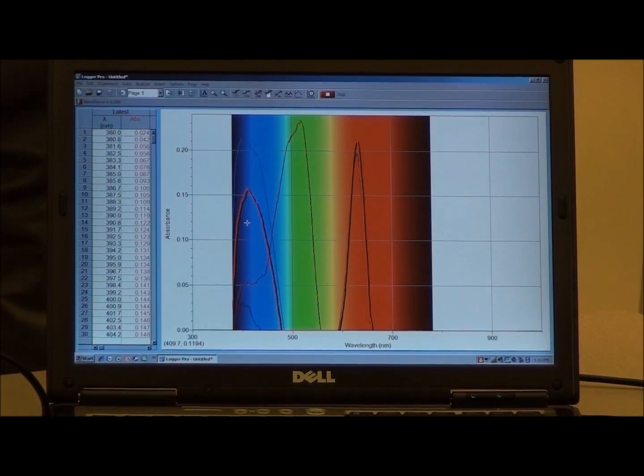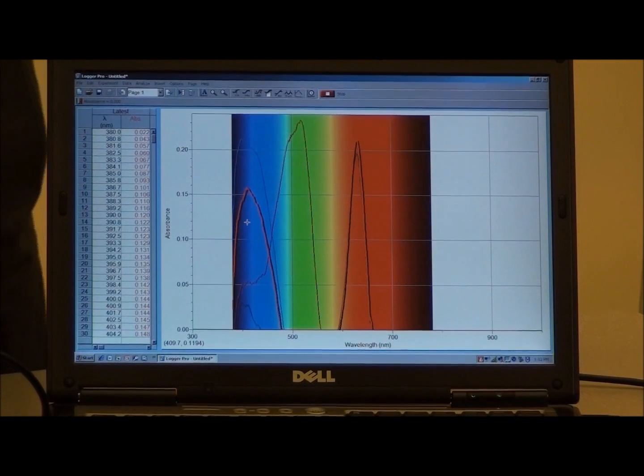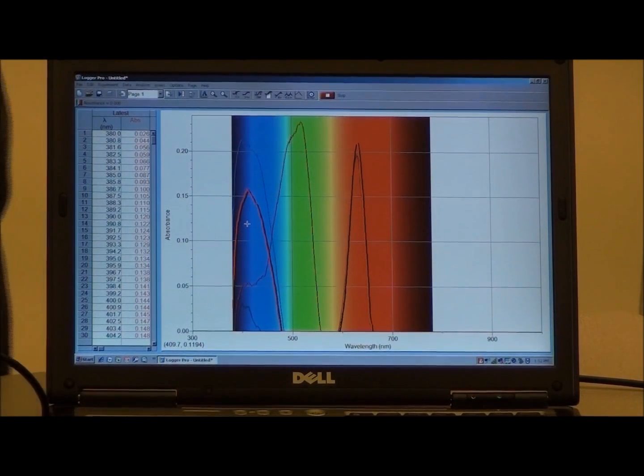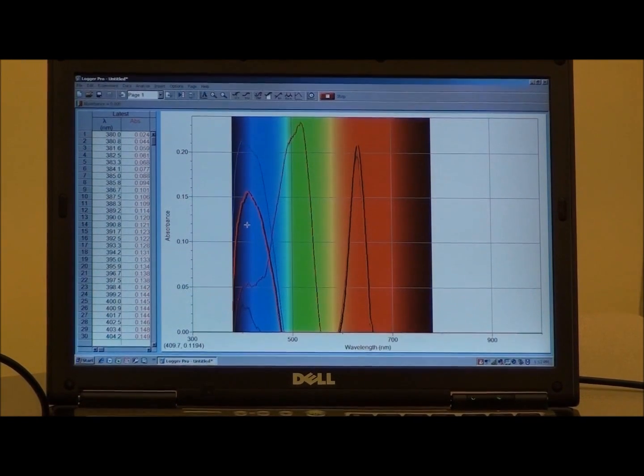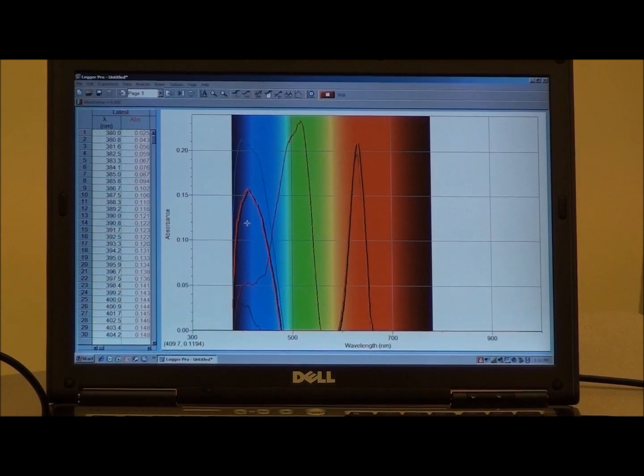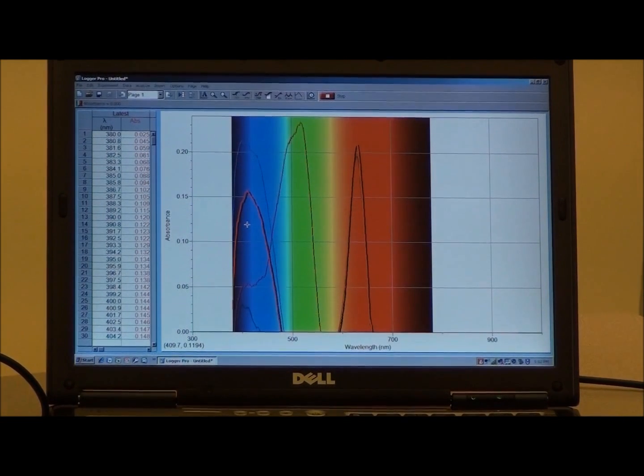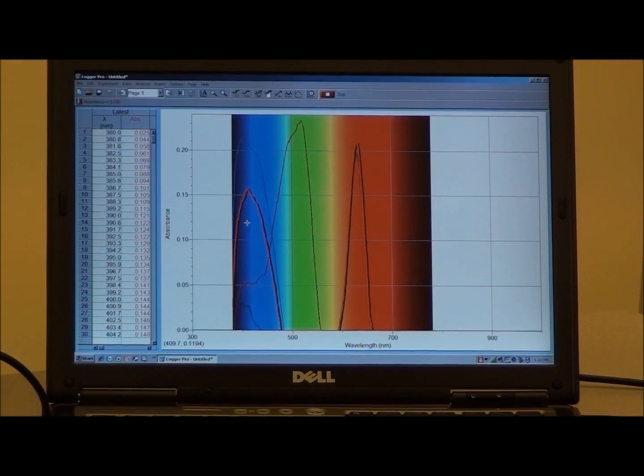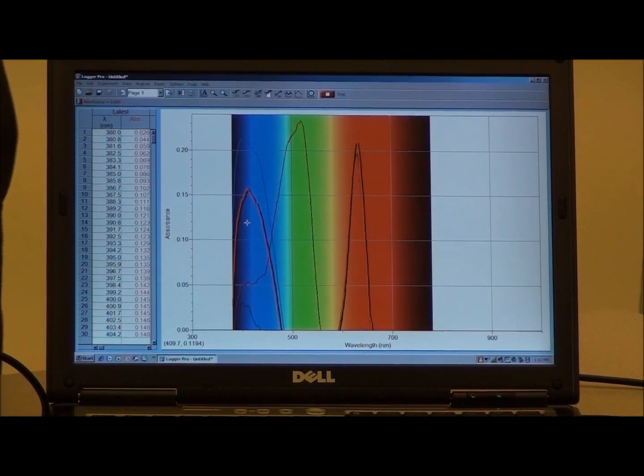In summary, we have seen that pulse oximetry is a methodology based on the absorption of electromagnetic radiation by oxygenated and deoxygenated hemoglobin at two different wavelengths. In this particular case, 660 and 940 nanometers. Based on these interactions, the pulse oximeter can easily determine the percent SpO2 in the blood and the heart rate.